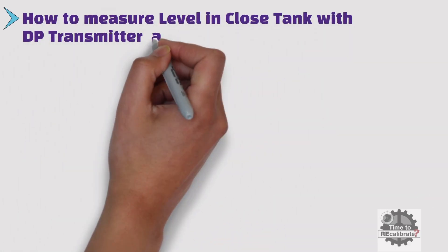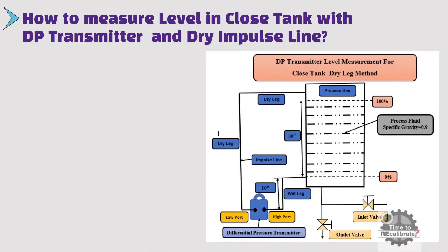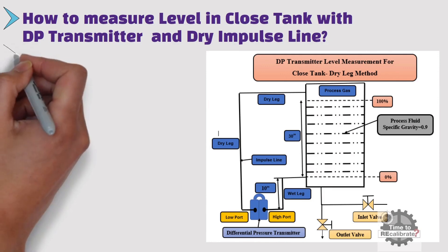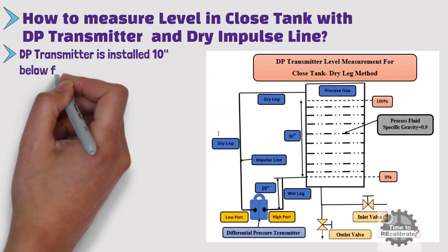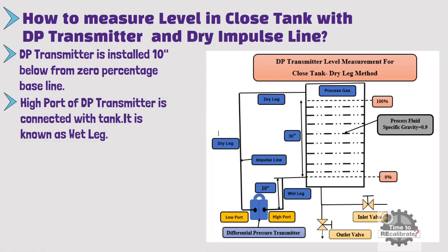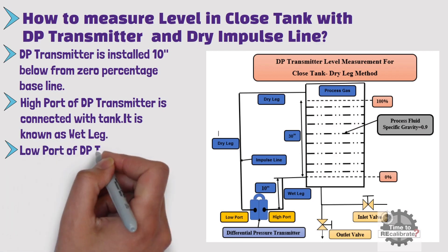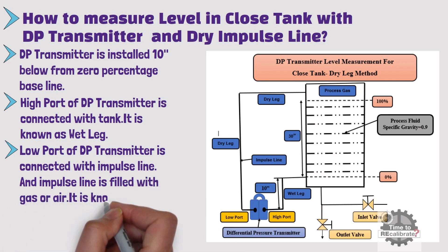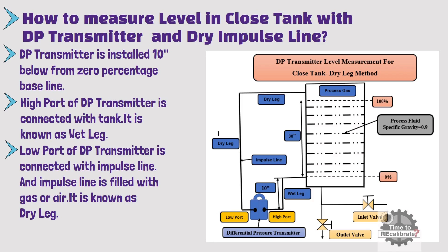Now, how to measure level in a closed tank with a differential pressure transmitter and dry impulse line. This method of liquid measurement is also known as the dry leg method. As you can see from the picture, the differential pressure transmitter is installed 10 inches below from the 0% baseline. The high port side of the DP transmitter is connected with the tank, and the process fluid puts pressure on the high side — this is also known as the wet leg. The low port side is connected with an impulse line filled with gas or air, which does not put any pressure on the low port side. The height of the dry impulse line does not affect level measurement, so the low port side has 0 inch H2O pressure.